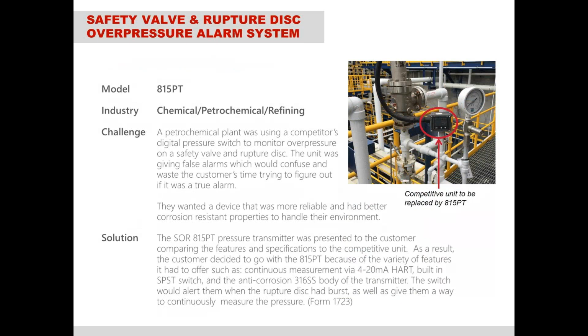This is a rupture disk application for a chemical plant for refining. They need to monitor the pressure coming off of a rupture disk, which is literally a disk designed to burst at a predefined pressure. When this disk bursts, there's really no way to tell unless you have a pressure switch or a pressure transmitter there. So they were using our pressure transmitter in line with it to monitor that rupture disk. The switch would alert them or turn off something, while the transmitter gave them a continuous output to alert the operators, to possibly prevent the rupture disk from rupturing to begin with.